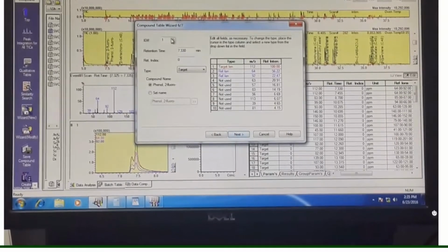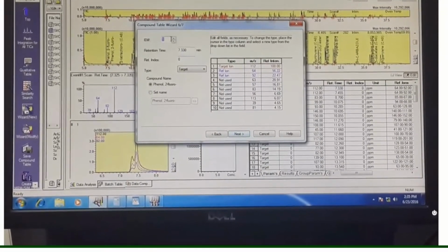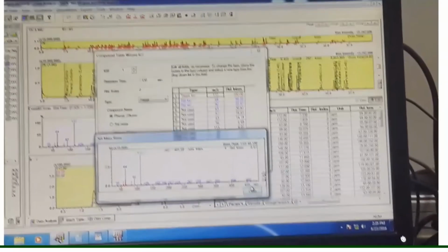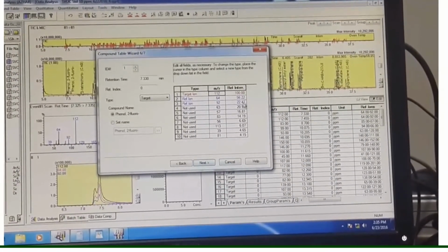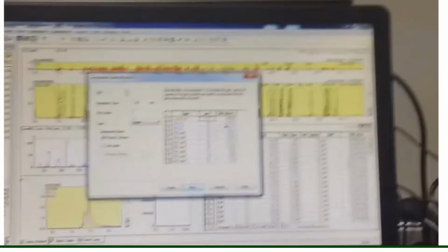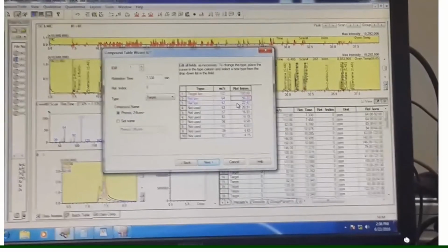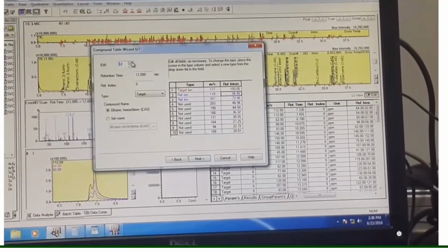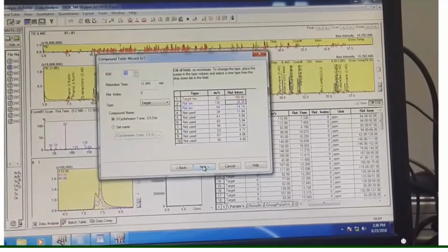Next, it will show you, for compound number 1 through all the compounds that we already named before, the fragmentation pattern for each one. If you want to show it again, just press here and you will see. It will show you the target ion, which is 112, which reference ions have been selected, and the reference intensity of each reference ion relative to the target ion. Like this one, the first one has about 56%, and the second one has 22% of the target ion. This will change, and you can check it for each compound.